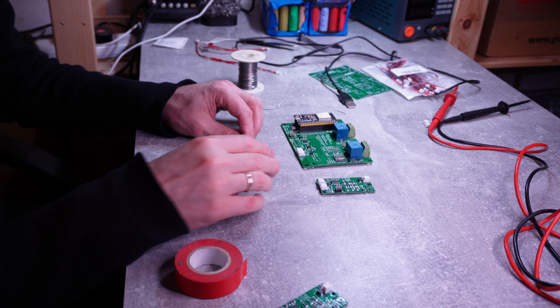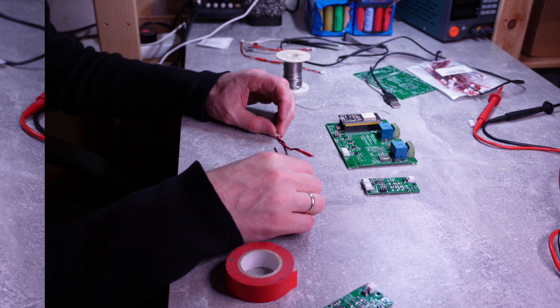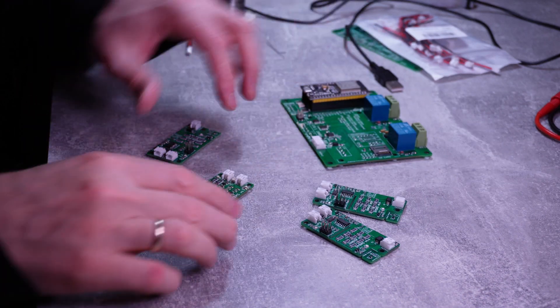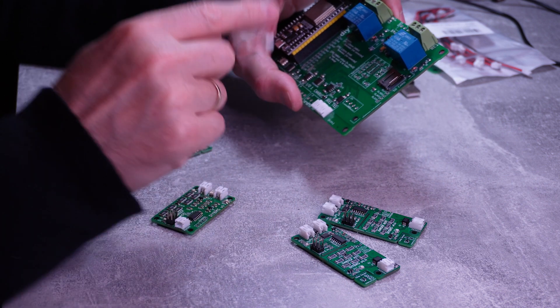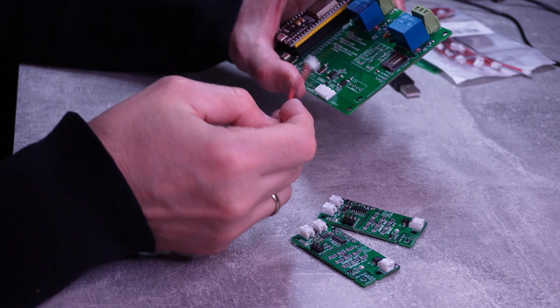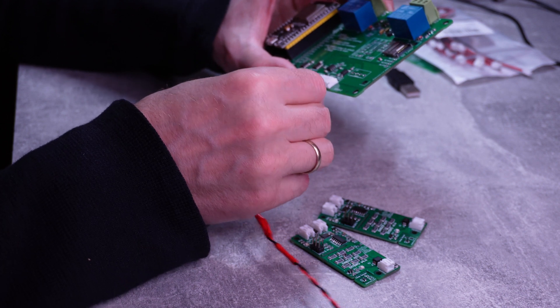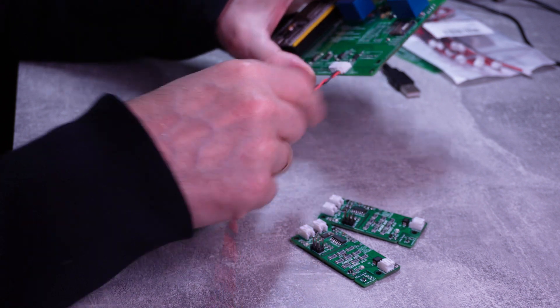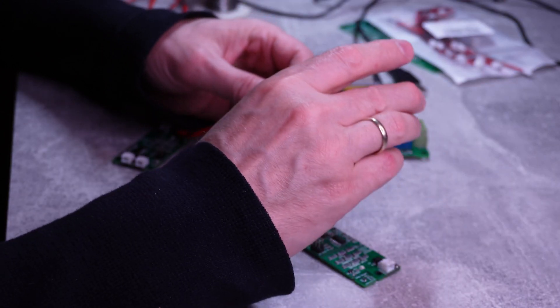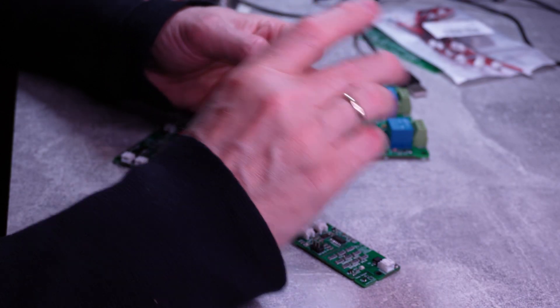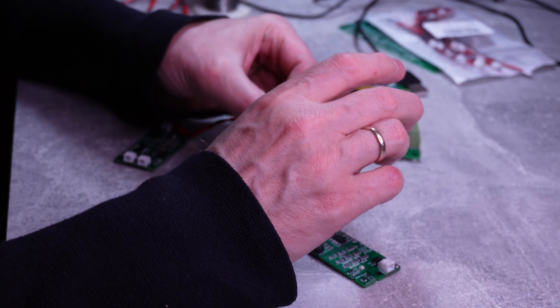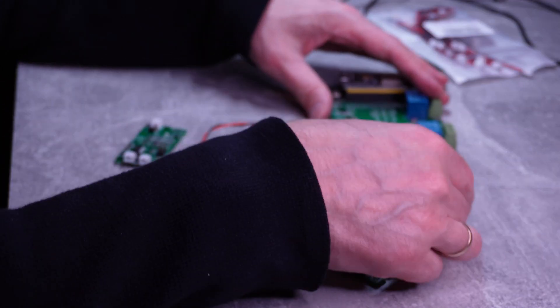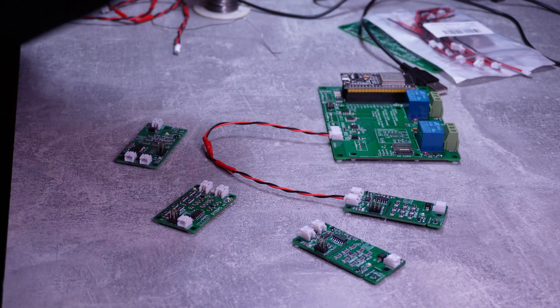And in this case they have to be crossed effectively. So now we can connect the modules. So the modules have to be connected in series. The controller has transmit-receive connections on it. So we will start from a transmit connection. And transmit connection should go into receive on the module. Which happens to be on this side here. So that's a connection between transmit and receive.